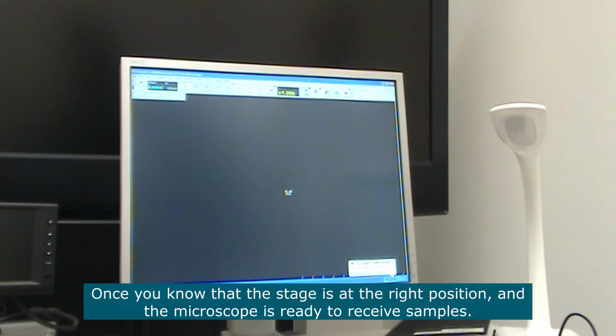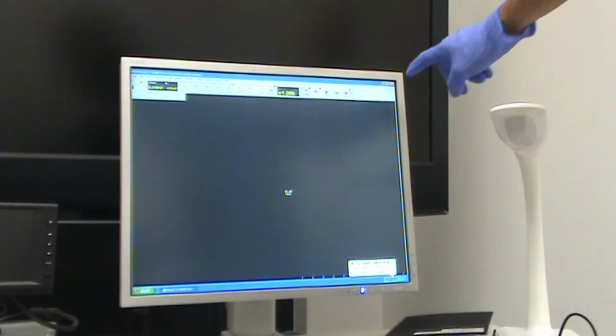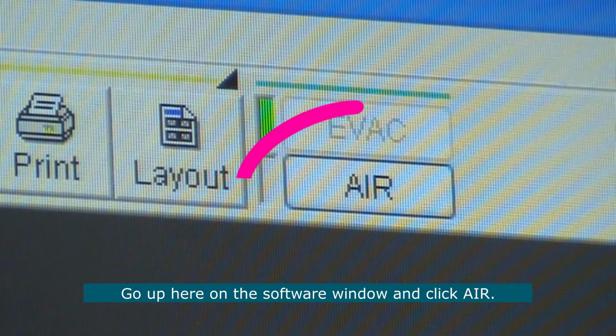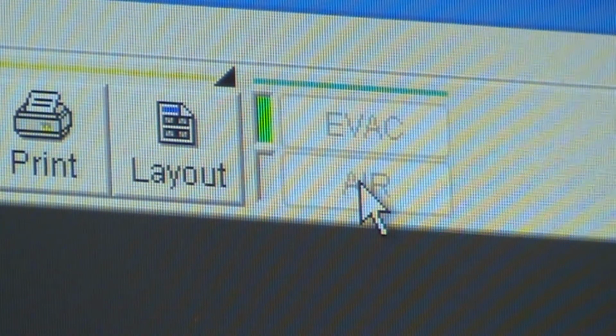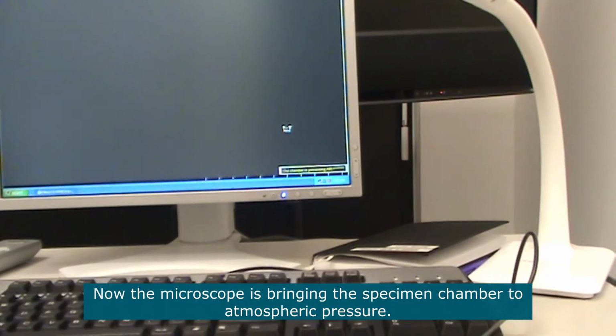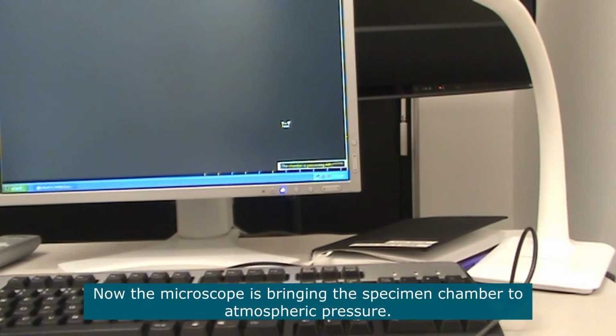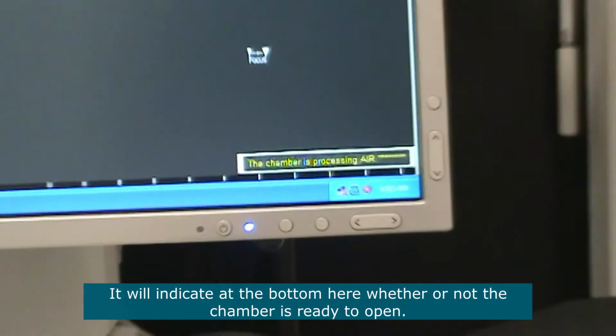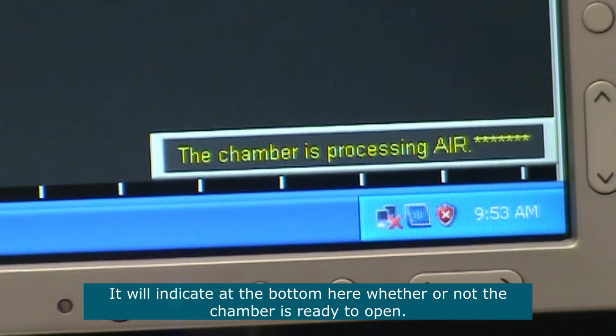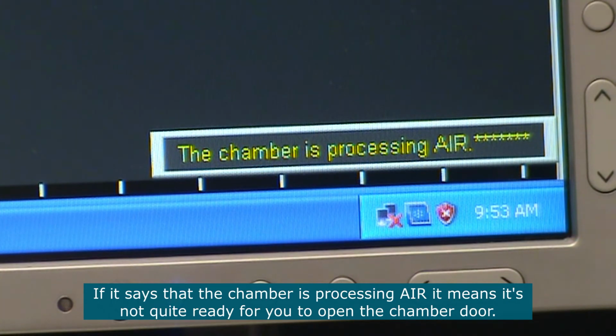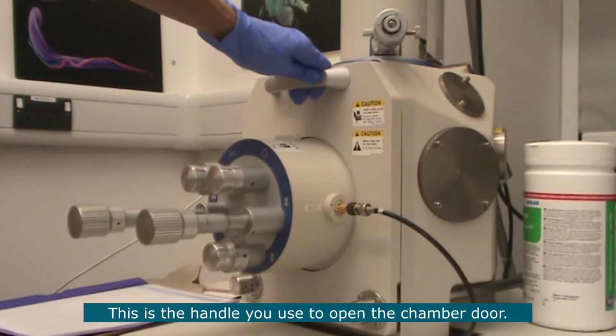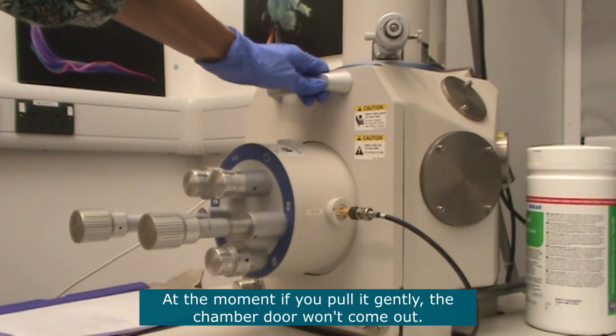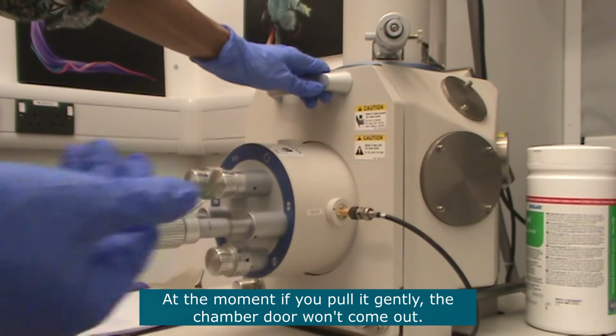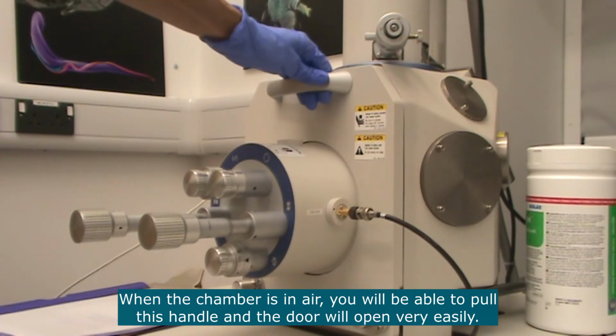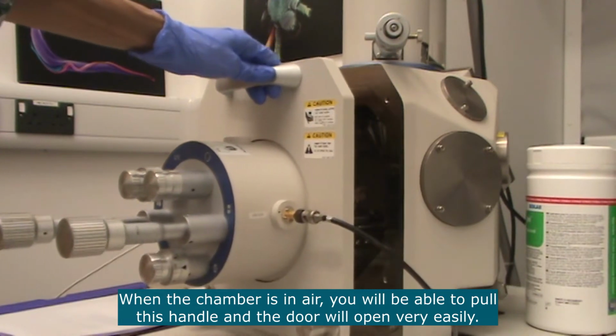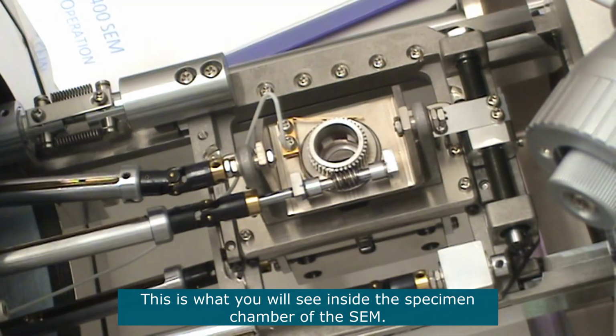Once you know that the stage is at the right position and the microscope is ready to receive samples, go up here on the software window and click on Air. What's happening now is that the microscope is bringing the specimen chamber to atmospheric pressure. So it will indicate at the bottom here whether the chamber is ready or not. While it says that the chamber is processing air, it means it's not quite ready for you to open the chamber door. This is the handle you use to open the chamber door. At the moment, if you pull it gently, the chamber door won't come out. Once the chamber is in air, then you will be able to pull this handle and very easily the door will open. This is what you will see inside the chamber of the SEM.